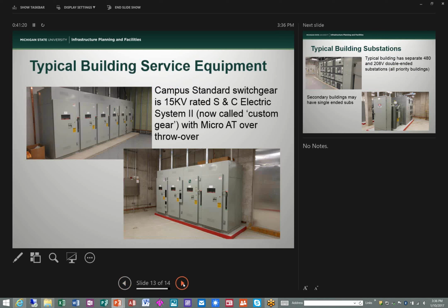So just like over the holiday break, we did a lot of converting of circuits, as I mentioned, the Kellogg Hotel, the Brody Complex. Simultaneously, Rick had breaker maintenance to do on bus 2 back at the plant. So we needed to clear bus 2, and this gear arrangement allows our guys to go out to the field and close transition transfer between the two without the building taking an outage. We can go from the preferred circuit to the complement without any interferences, without dropping the load.